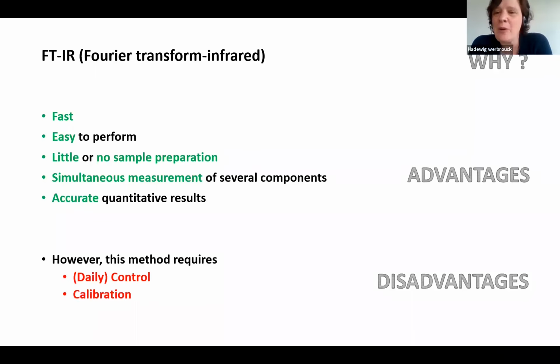Why? Compared to the reference methods, which are usually slow, difficult, expensive, and time-consuming, the FT-IR method is fast and easy to perform. The method also requires little or no sample preparation, and it can measure several components at the same time. It also delivers accurate quantitative results. These are the advantages of the FT-IR. However, this method requires daily control if you use the system daily, and calibration to obtain accurate quantitative results.